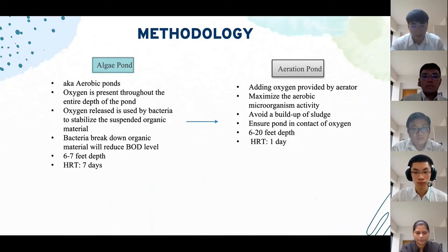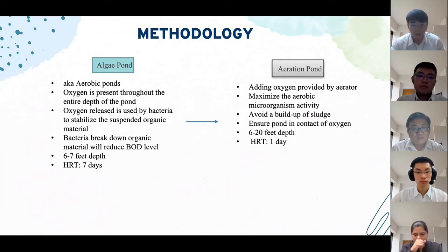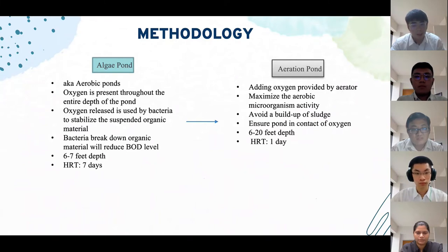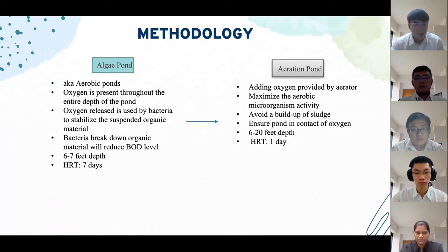Moving on to the last pond, which is the aerated pond. Oxygen provided by aerators is added to increase dissolved oxygen levels in the pond, thus maximising aerobic microorganism activity. The aerated pond is also used to avoid build-up of sludge and to ensure the entire pond is in contact with oxygen. This pond is usually 6 to 20 feet deep with an HRT of only one day. After passing through all these ponds, the effluent is now safe to be discharged. That's all from me; I will now pass the floor to Yin Liang.